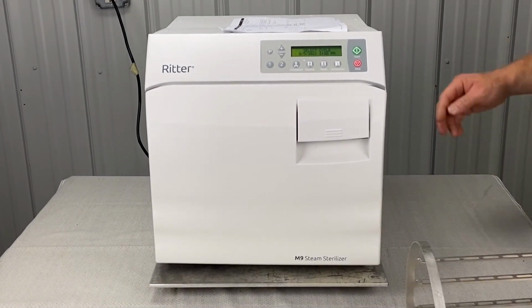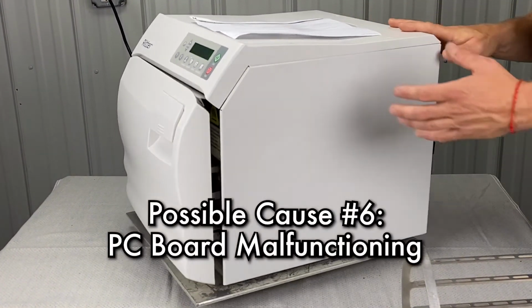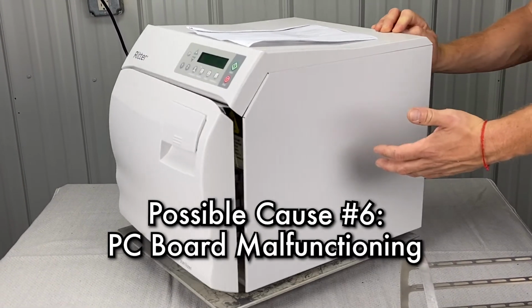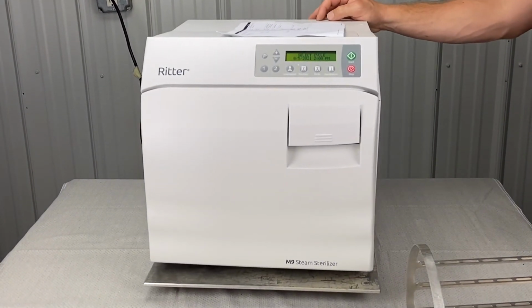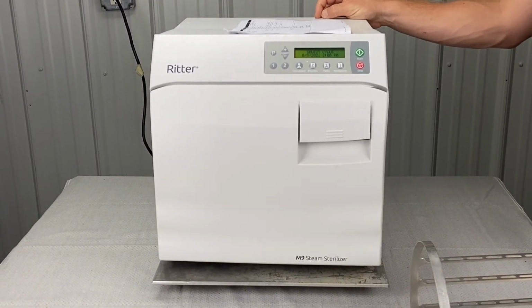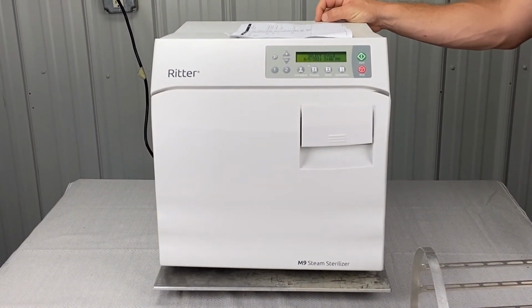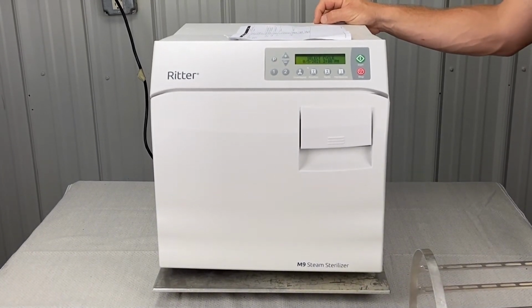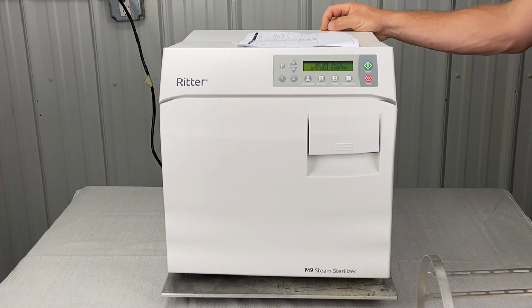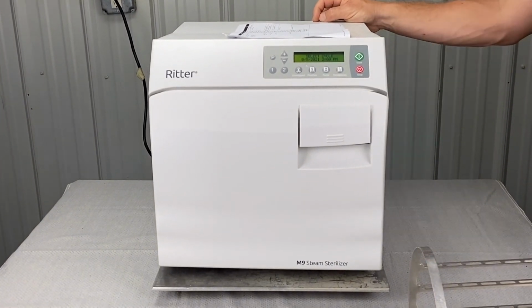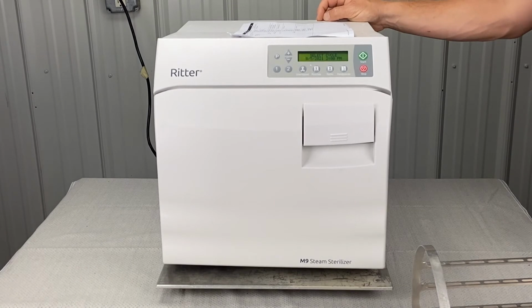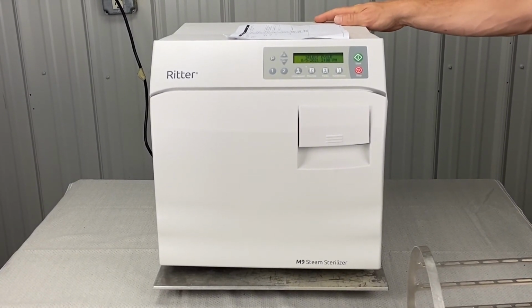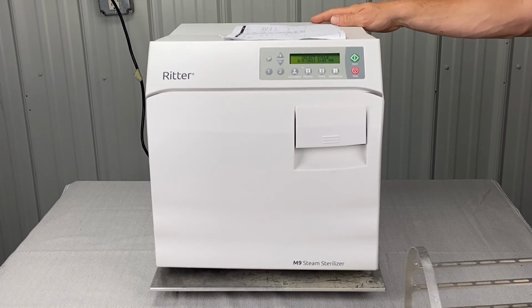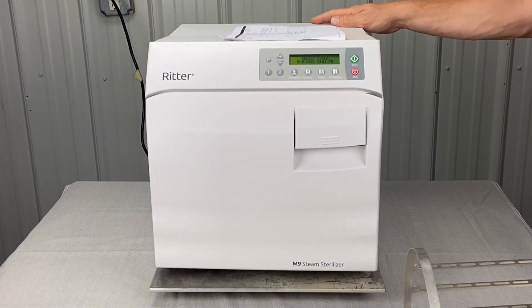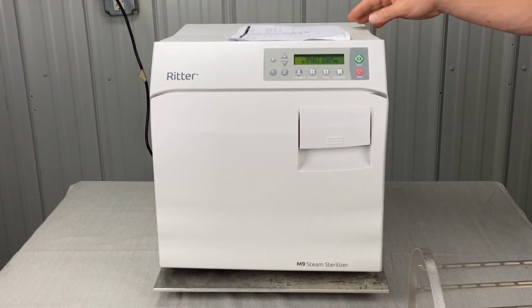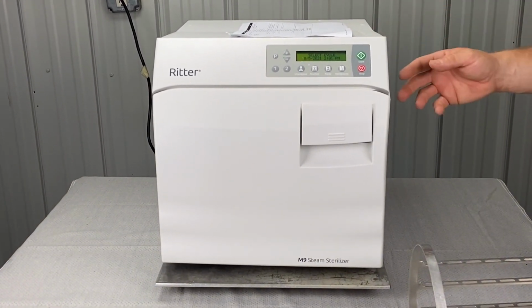And then furthermore, it would be a PC board. Again, we can take the right side panel off and look at the PC board. You'd have to have an inductive ammeter and a multimeter, and we can perform any number of tests in diagnostic mode. It would be a heating element supply voltage test, making sure that the relay is functioning properly and the PC board is actually pushing out volts to the heating element. And then the main PC board relay test, and then the main PC board pressure transducer voltage test. So these are all things that we'll have to dig a little deeper for.